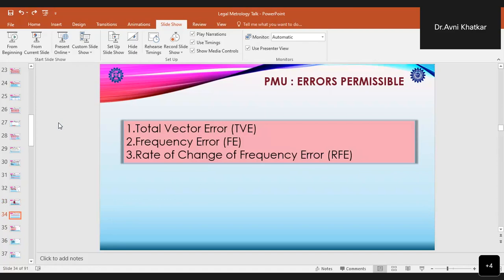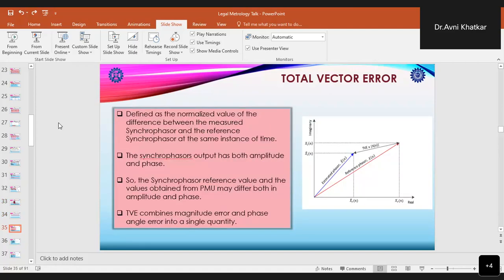Now, when we talk about PMUs, we talk of errors in three quantities: total vector error, that is TVE, frequency error, that is FE, and rate of change of frequency error, that is RFE. So we will see all of these here. First one is total vector error. Total vector error is defined as the normalized value of the difference between the measured synchrophasor and the reference synchrophasor at the same instant of time. These synchrophasor outputs have both amplitude and phase, so the reference value and the values obtained by the PMU may differ in both amplitude and phase. Total vector error combines both the magnitude error and phase angle error into a single quantity.